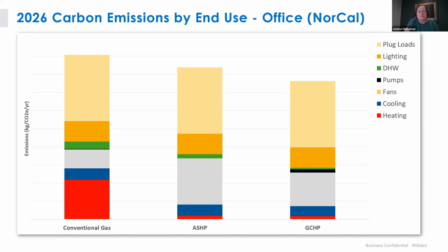However, the type of system we used was a distributed air source heat pump system, which increased the fan energy of the building. So if we really wanted to get back to that lower fan energy we're seeing in the first option, we could try utilizing a heat recovery chiller instead. I think we'd see a big reduction in fan energy and a further reduction in the emissions of the all-electric option. So that would be something to consider.